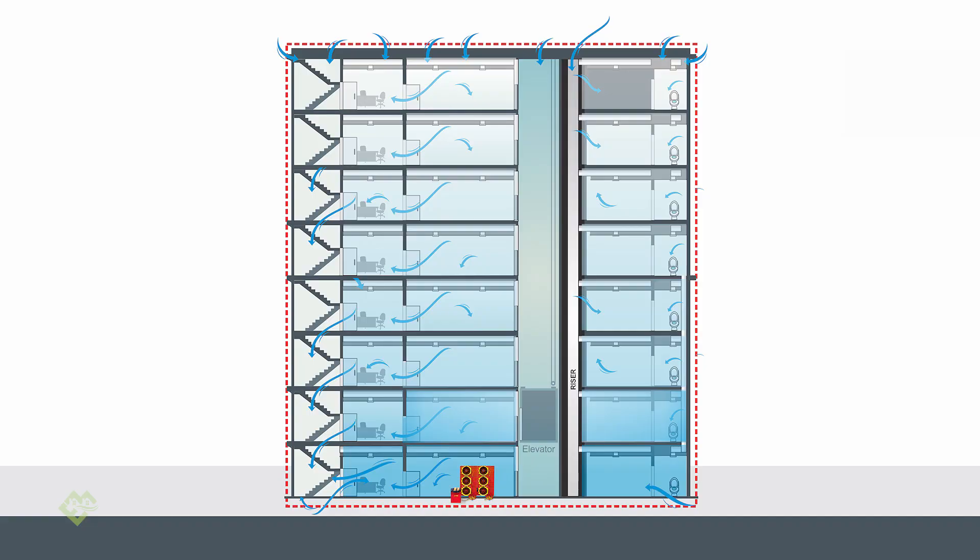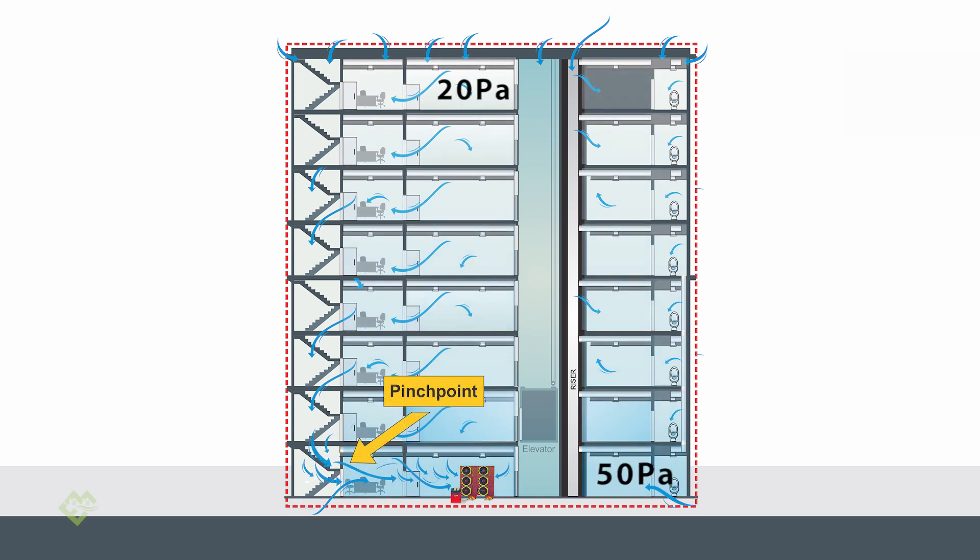For any buildings that are 20 metres cubed per hour per metre square, you're pretty much guaranteed to have pinch points. The leakier the building, the harder it is to test. To make the case simple, it's like filling a bucket with just one hole — you can use a garden hose to fill it up even with one hole leaking it out. But if you've got a sieve there, there's no way you can fill it.